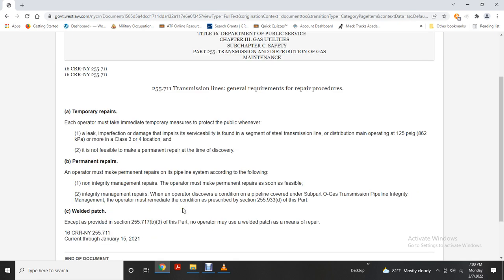Permanent repairs. The operator must make a permanent repair of the pipeline system according to the following. Non-integrity management repairs: the operator must make permanent repairs as soon as feasible. Integrity management repairs: when an operator discovers a condition on a pipeline covered in subpart O of the gas transmission pipeline integrity management rule, the operator must remediate the condition as prescribed in 255.933 of this part. Except as provided in 255.717(b)(3) of this part, no operator may use a welded patch as a means of repair.